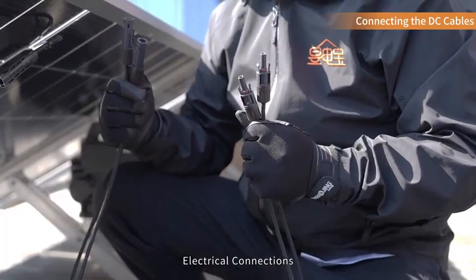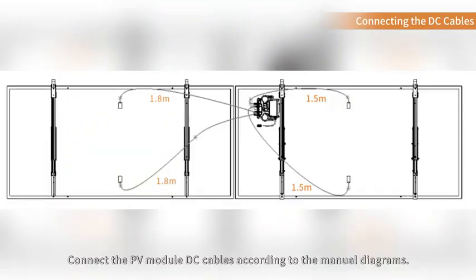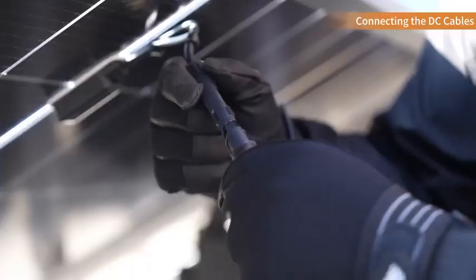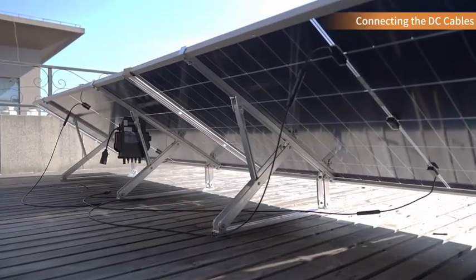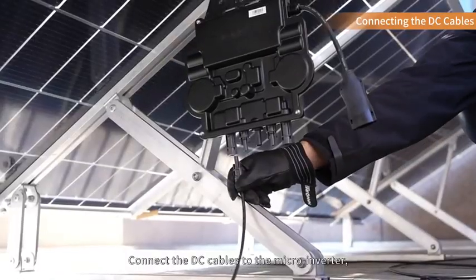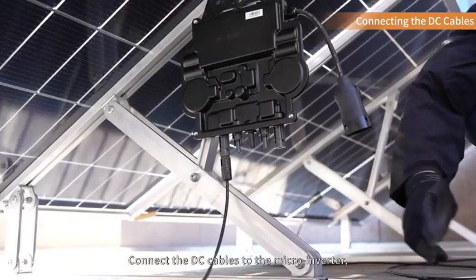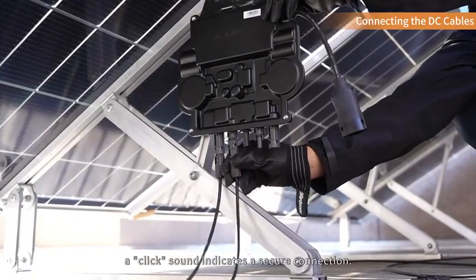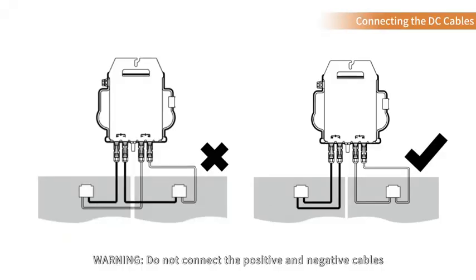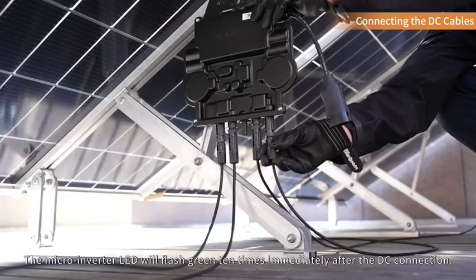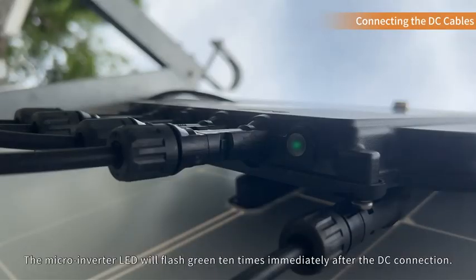Electrical connections. Connect the PV module DC cables according to the manual diagrams. Connect the DC cables to the microinverter. A click sound indicates a secure connection. Warning: do not connect the positive and negative cables of the same module to different input channels of the inverter. The microinverter LED will flash green 10 times immediately after the DC connection.